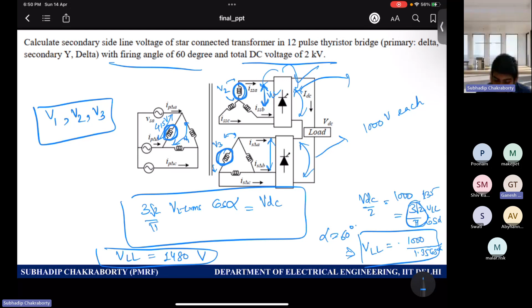V1, V2, sir, 30 degrees. V1, V3, no phase shift. No, you are memorizing. 30 degrees, why? Star and delta line voltages are 30 degrees apart. But for a transformer, if one coil is primary, one coil is secondary, another coil is tertiary, there would not be any phase shift, because transformers are meant to be magnifying or reducing the voltage amplitude levels, coil to coil, phase to phase. So for a transformer, phase to phase transformation happens on magnitude, they are not phase displaced.